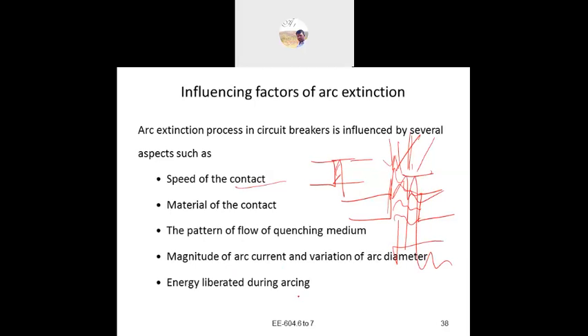Next, the energy liberated during the arcing: how much energy is liberated due to the arcing. If less energy is there, the arc is easily extinguished. But if the energy is high, then the arc is also very high. So low energy means a low-current arc, and high energy means a long arc flow. That is the difference.